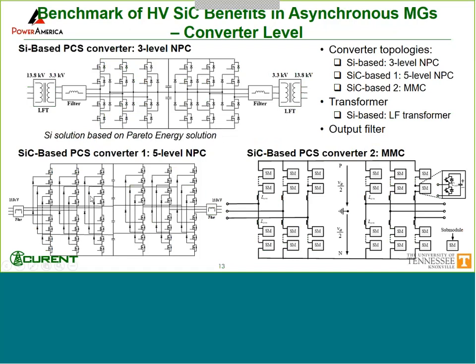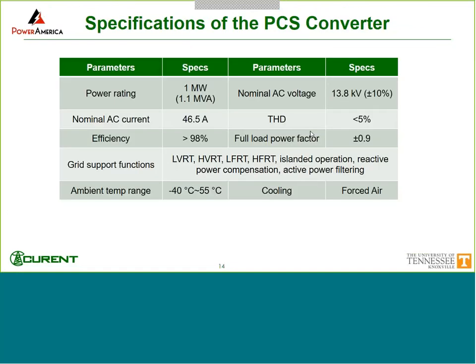So let me start with the benchmark of the converter. And we have done basically three comparisons. And the first one is a baseline with the silicon. That is a similar picture I just showed with 3.3 kV AC voltage and through a transformer to 13.8 kV. And then two silicon carbide based topology, one is a five level NPC, the other is MMC. So in both cases, we have done exactly the same design for the same spec. And here is the spec we have used. Basically, it's a 1 megawatt design.